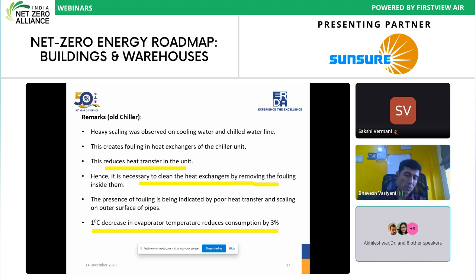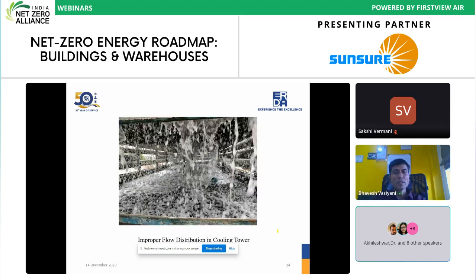This is a thumb rule. Improvement in the temperature of the evaporator or condenser will affect the power consumption of the chiller directly. Similarly, a cooling tower is always there for condenser water cooling. So ultimately, the chilled air heat load is transferred to the chilled water. Then the chilled water heat load is transferred to the cooling water. That cooling water is getting cooled by ambient air through the cooling tower. The cooling tower is mechanical, meaning an induced draft cooling tower is there. But here, for the old chiller, we can see that there is unequal water distribution. It is not like a normal cooling tower with continuous, distributed water distribution. It should be spread across the cooling tower so that the evaporative cooling effect can be achieved in this cooling tower. So this was another area.